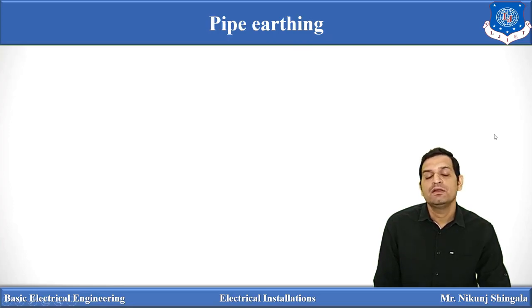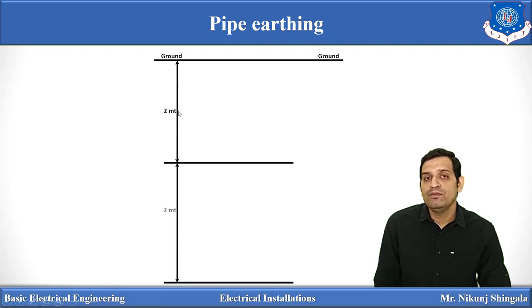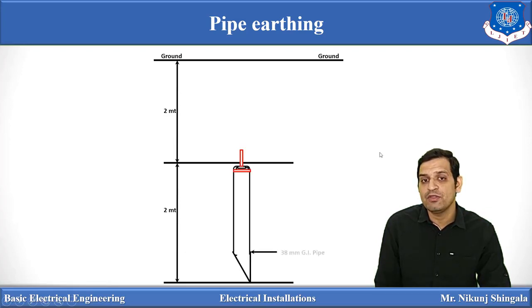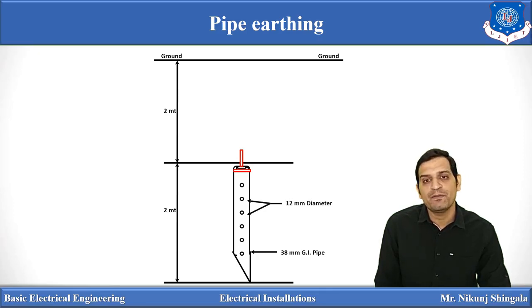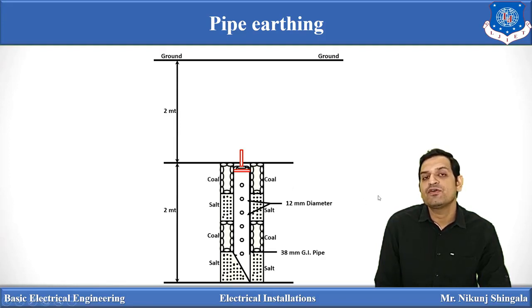For the pipe earthing method, a 4-meter pit is dug below the ground. Below 2 meters from the ground surface, one galvanized iron pipe of 38 mm diameter is used, and that pipe has different holes of 12 mm diameter, basically used for water pouring. Around this galvanized pipe, alternating layers of charcoal and salt — each 15 cm by 15 cm — are placed. The function of these alternating layers is to increase moisture and area around the galvanized pipe so that resistance can be decreased.